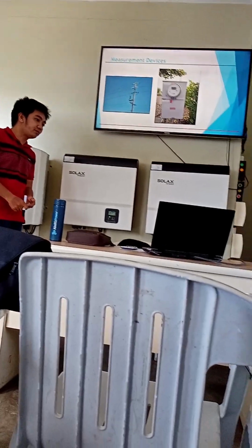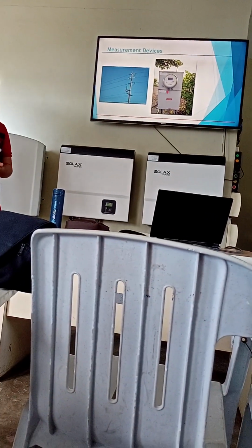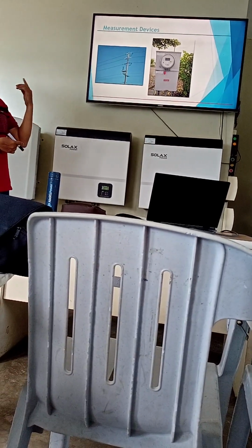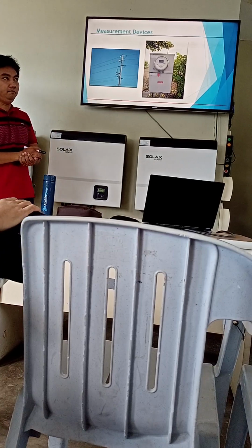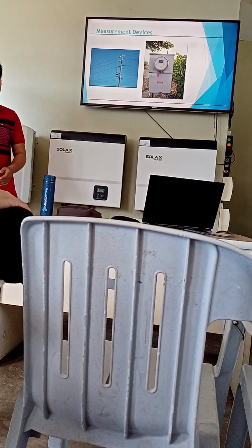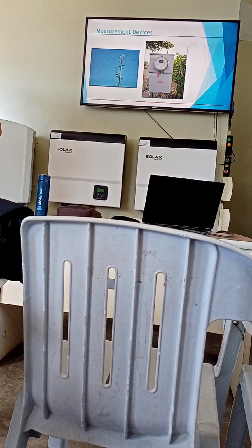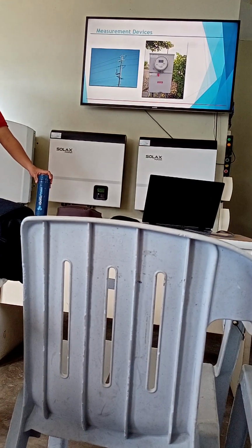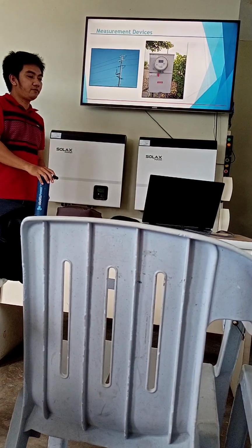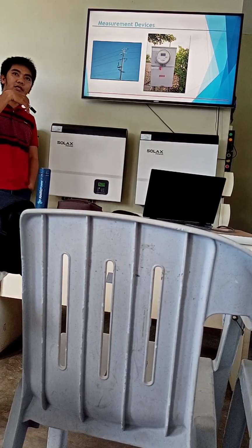Aside from the transformer, we have the measurement devices. You see them not only in the substation but also in our distribution lines, on the power transformer or the distribution transformer of industrial companies that are primary metered. In Sipalco, for example, these are the customers under schedule 58: customers with specialized voltage and a power requirement above 500 kVA. Once your customer classification reaches schedule 58, you are automatically primary metered. With primary metering, the losses in your transformer will be charged to you.